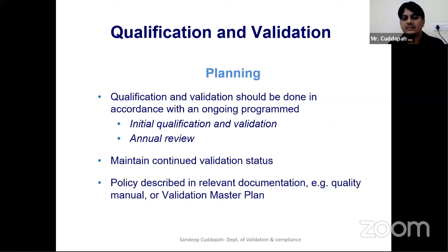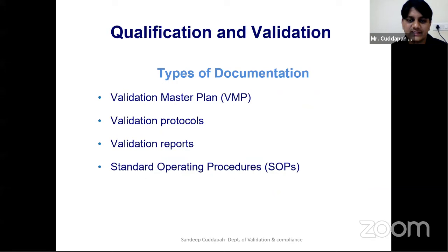The first thing that comes in this is planning. Qualification and validation should be done in accordance with an ongoing program. It is not only done initially for anything. With a certain frequency, you have to repeat this qualification so that your equipment is maintained throughout its lifetime, to prove that you will give a certain frequency based on the criticality.